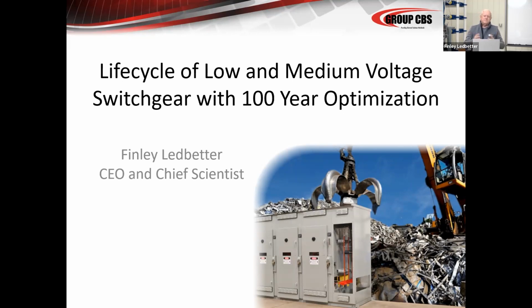You have to move a lot of mass, a lot of distance, so you have to have a big, tough mechanism. You have to have a lot of springs, and age, time and heat affect springs. So everything was working against the air breaker in comparison to the vacuum breaker. The vacuum breaker moves a very small amount of mass, a very small distance, so the mechanism can be very light. There's not as many springs, there's not as much energy, as much WK squared involved.